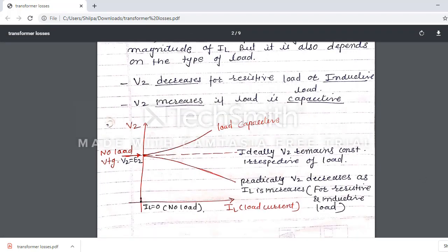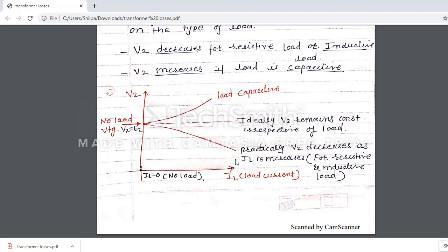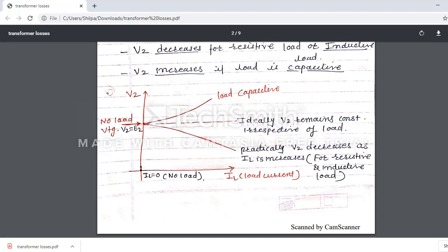This is the graph of regulation, showing terminal voltage V2 versus load current. At no load, IL is equal to zero, so V2 is equal to E2. Ideally, V2 remains constant irrespective of the load. For capacitive load, V2 increases. For inductive and resistive load, V2 decreases. This is the voltage regulation of a transformer, and the definition and this graph are important. Thank you.